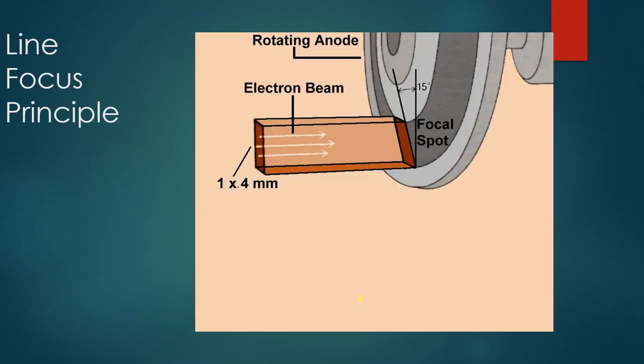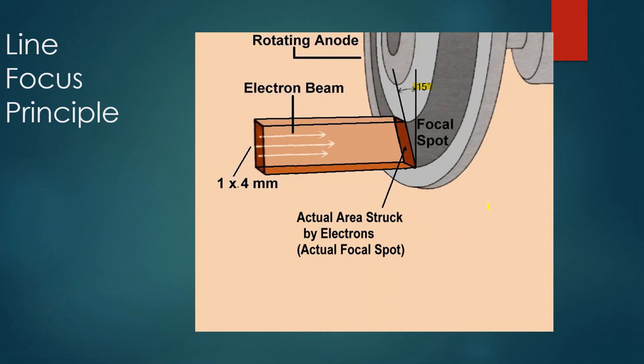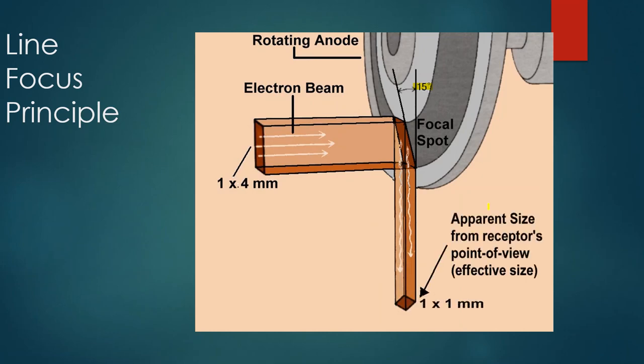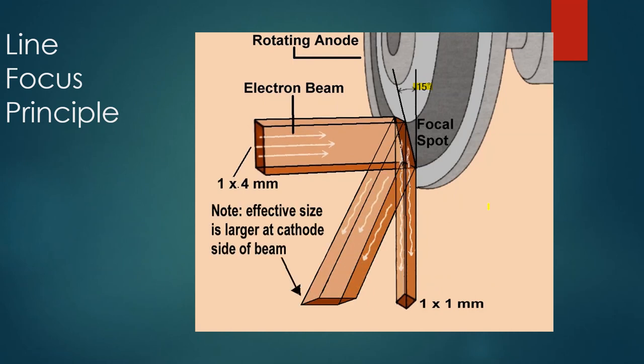The line focus principle: when the electron beam travels from cathode to anode, it is focused into a point — but it actually has an area, in this case approximately one by four millimeters. Due to the anode's bevel — in this case 15 degrees — the angle changes what is the actual area the electrons strike compared to the area apparent from the point of view of the receptor. The apparent size of the focal spot changes depending on whether we view it from the cathode side or anode side of the table, but the line focus principle states that the effective or apparent focal spot will always project smaller than the actual focal spot.